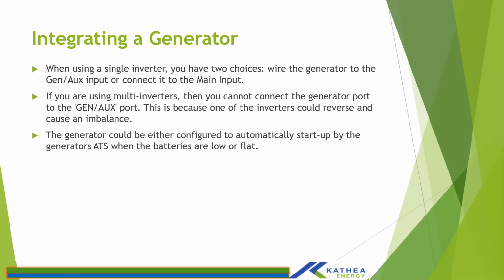If you are using multi-inverters, like you have said earlier, you cannot use the Gen Aux port. This is simply because it will cause imbalance within the inverters, and this could actually reverse power on inverters, which can cause imbalance of the system. So if you are paralleling inverters, whether in a single phase or 3-phase scenario, you cannot use the Gen Aux port. If you intend to use the generator, then you would need to install a changeover switch that will simply change between your grid and your generator, and then wire the output of the changeover switch to the grid point on the inverter.